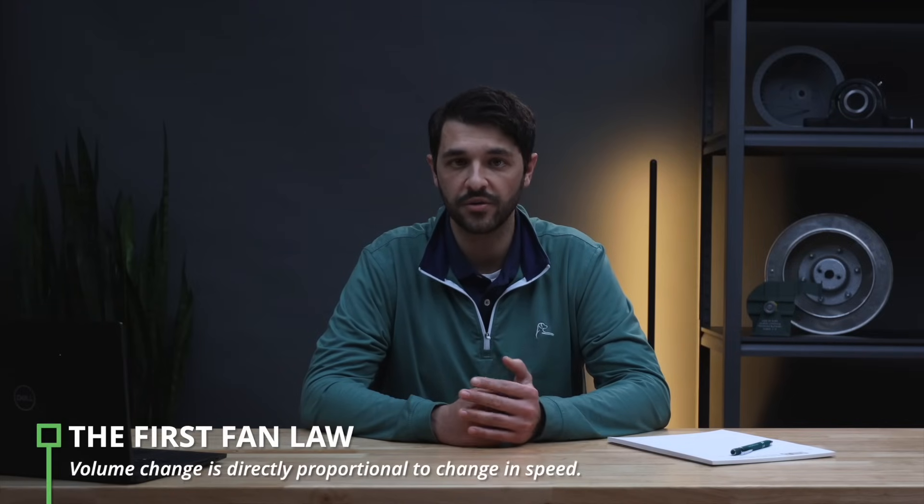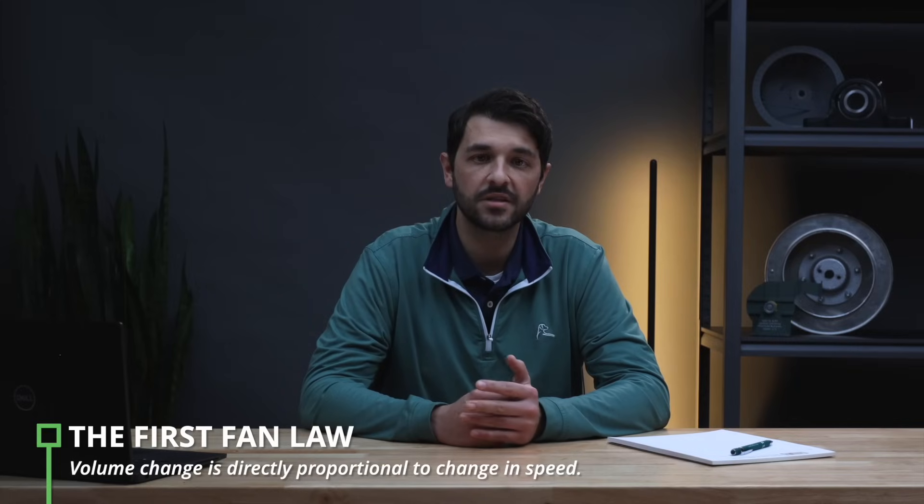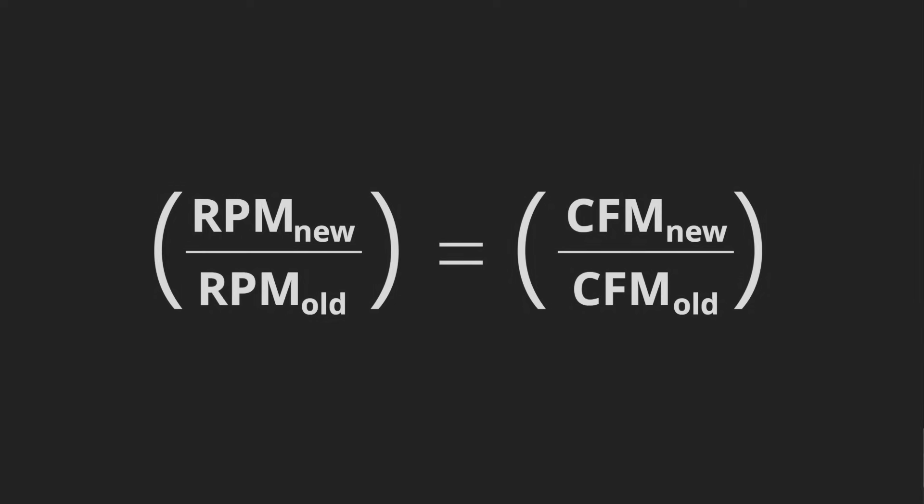With those concepts in mind, we can define the first three fan laws. The first fan law describes how airflow changes in response to a change in speed, and the change is a one-to-one ratio. This can be conceptualized by thinking of the blades on a wheel as a set of equally-sized shovels, each moving an equal amount of matter with each rotation. By changing the speed, you change the frequency with which each shovel moves an equal amount of matter — in other words, it changes at a one-to-one ratio. Algebraically, the change in speed (new speed divided by old speed) equals the change in flow (new flow divided by old flow).